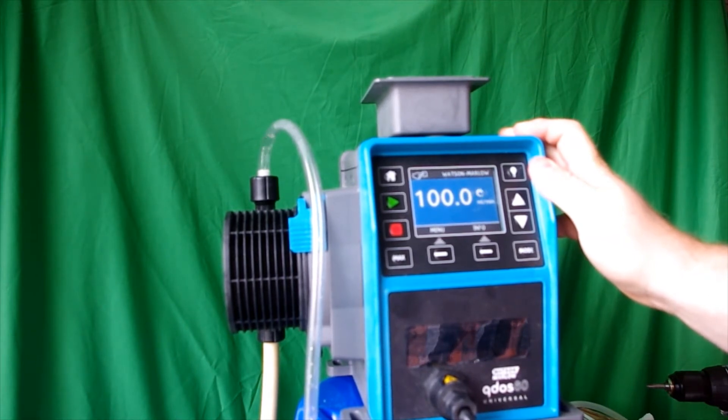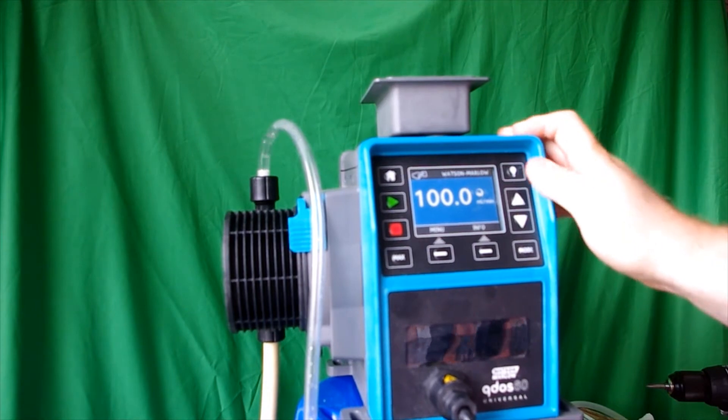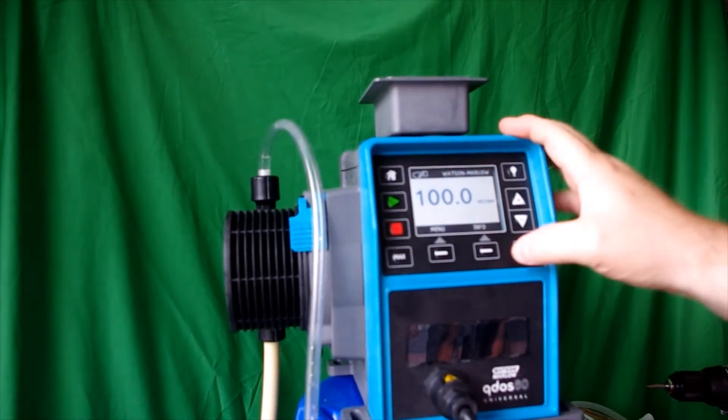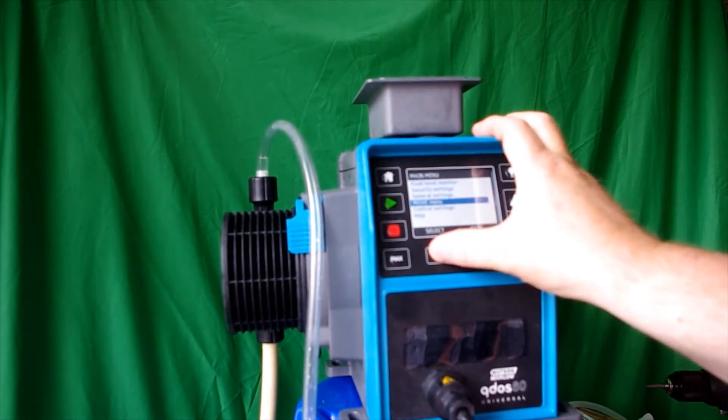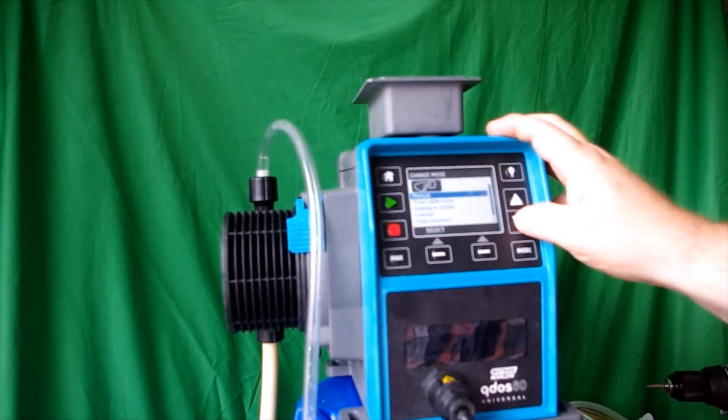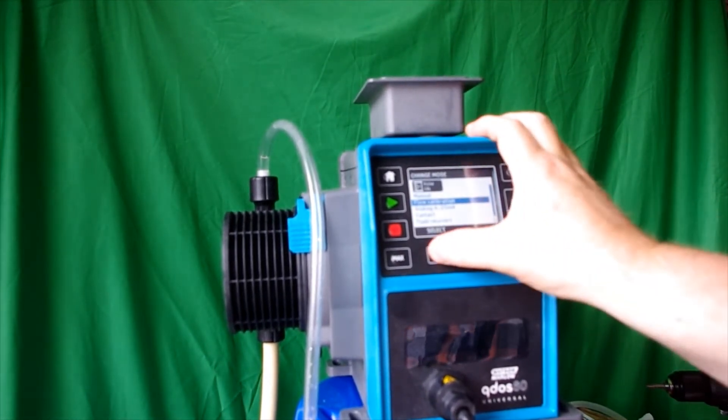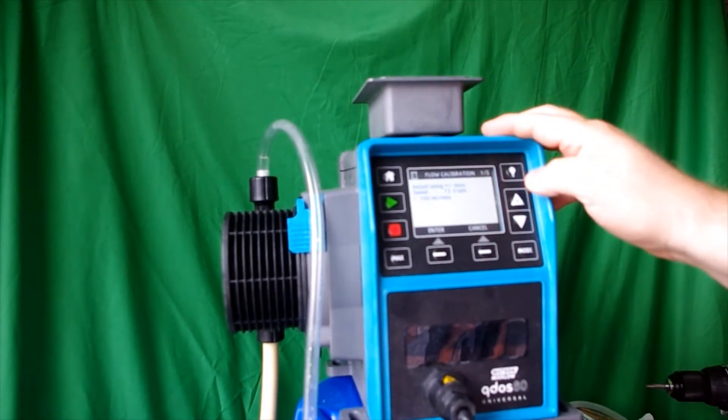Stop your pump, then you want to go into menu, you want to go into mode, you want to go into flow calibration which is the second feature down. Now it says what speed do you want to calibrate the pump. Since we're running around 100 milliliters per minute, we're going to calibrate it at that.